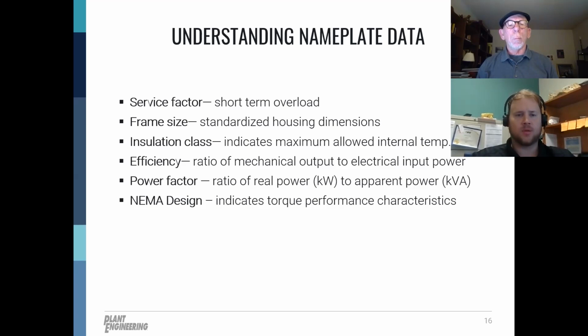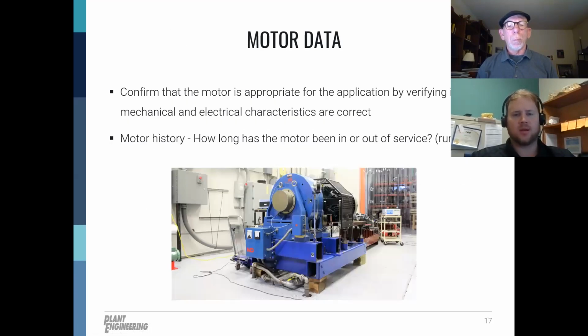So a few things to consider when you're looking at a motor nameplate or starting any kind of maintenance assessment. Well, what's the runtime of the motor? So, how often does the motor run? Is it running 24/7, 365? Is it running just a couple times a day? Is it a couple times a week? Runtime is very important to some of the maintenance programs, and then how critical the motor is to your facility. What is the application? How long does it run? Also, how long has it been in service or out of service? If it's not working, if the motor's failed, how long has it been failed? Do you have a backup that you store on site, or do you have a backup that your distributor stores for you?